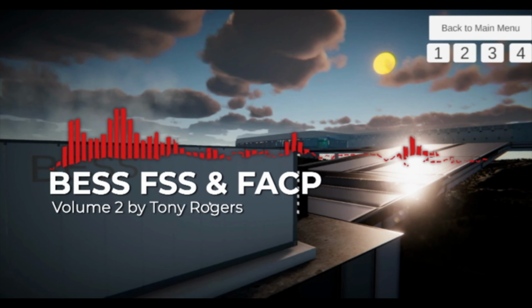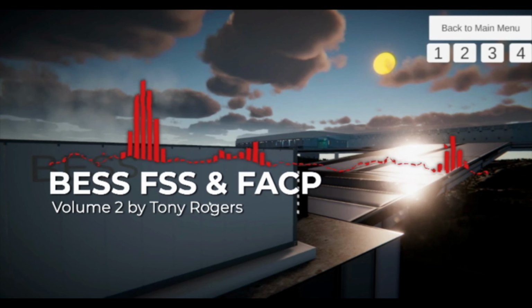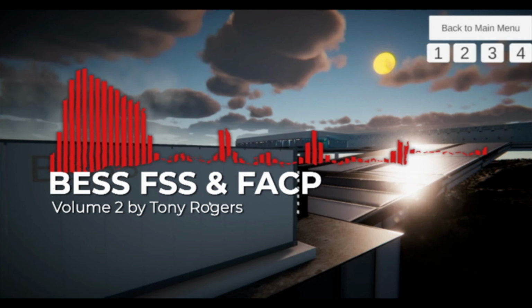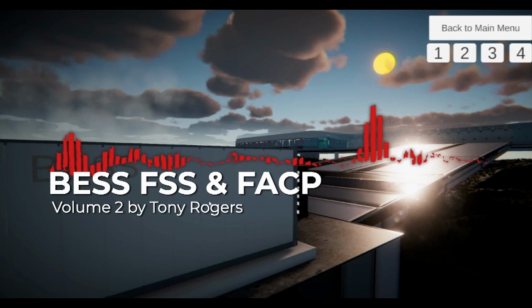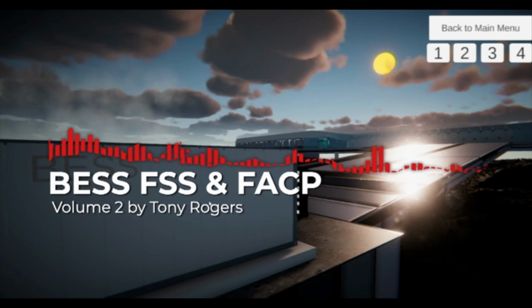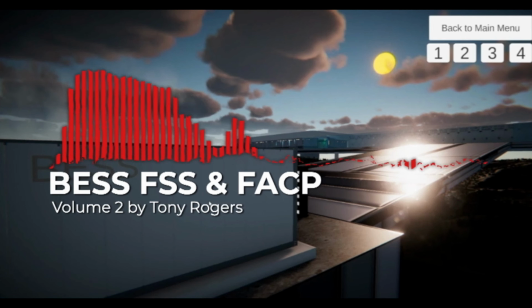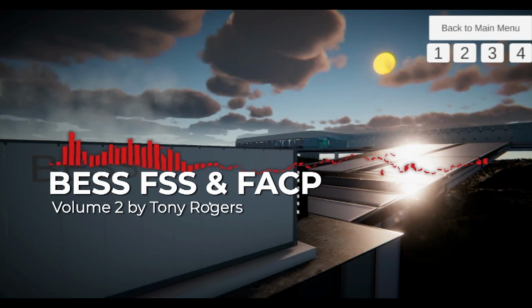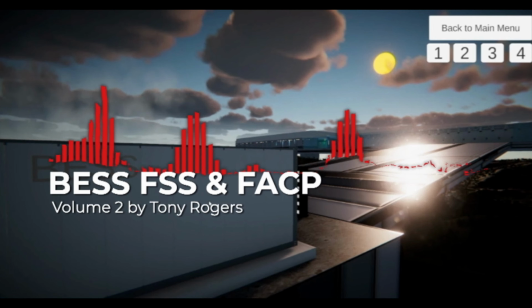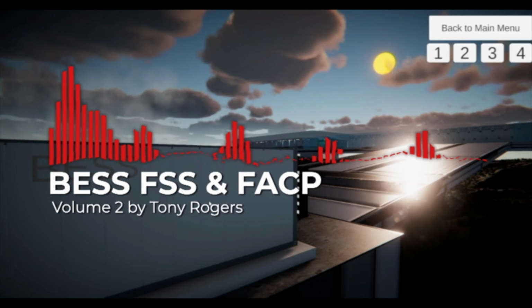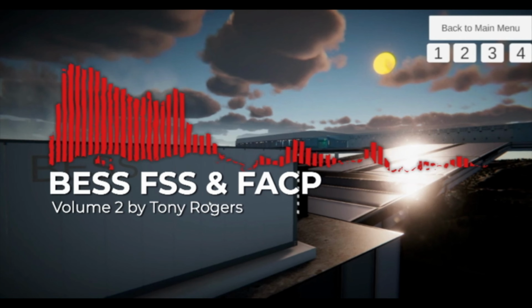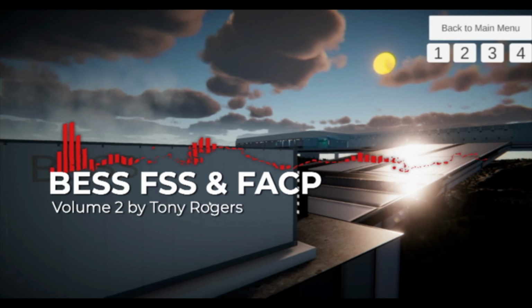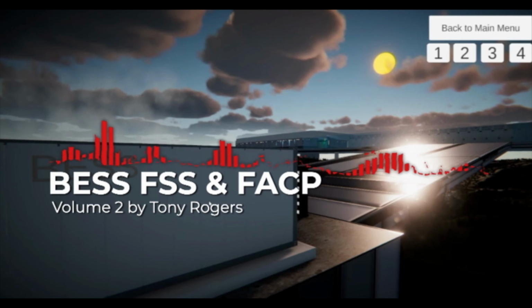Gas detection and management. Gas detection plays a crucial role in fire suppression systems as it enables the early detection of hazardous gases and facilitates timely response actions. BESS fire suppression systems utilize advanced gas sensors to detect hydrogen, carbon dioxide, and carbon monoxide. The concentration of gases in the protected area is measured using sensors, and the information is processed by the fire alarm control panel. Let's examine the gas detection formulas.